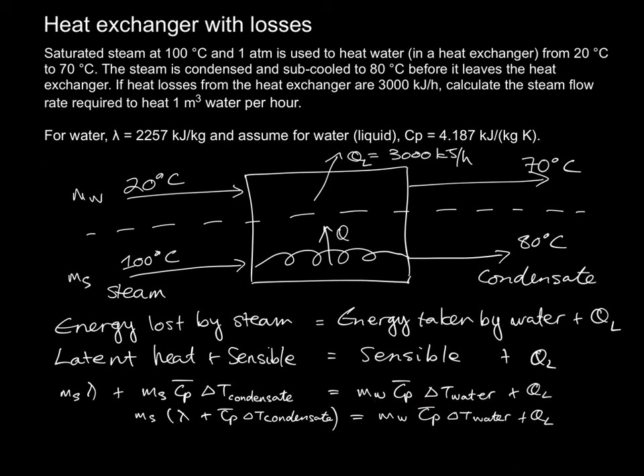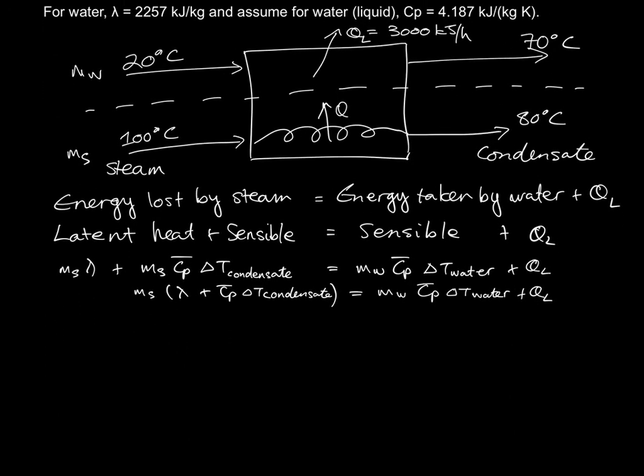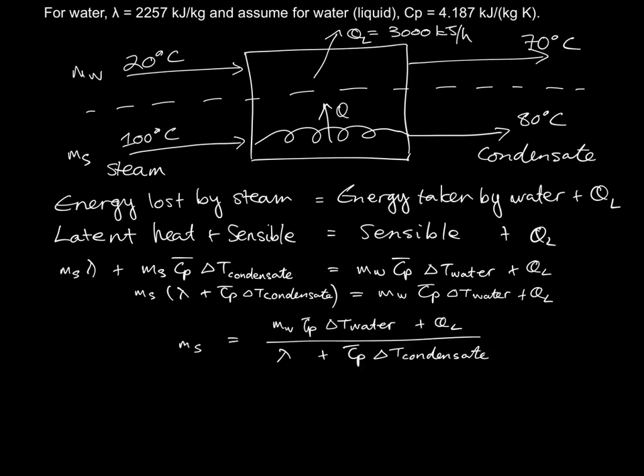We are now ready to do the substitutions. We can simply substitute. We have a flow rate for the water given in cubic meters per hour but we'll assume that one cubic meter is a thousand kilograms. We have Cp's of water given. Delta T water is this difference over here. Delta T condensate is this difference over here and our losses are given.